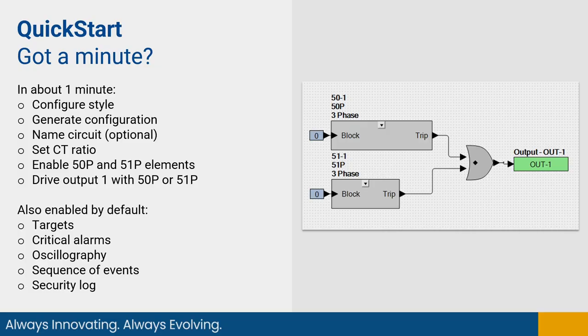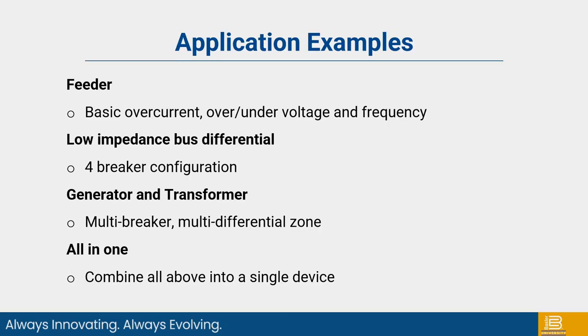The last step before saving the settings file would be to drag and drop the protective elements and other logic you may need and connect them on the logic page as shown on the right side of the graphic. Once these steps are complete and you save the file, you're ready to upload the settings file to your new BE1-FLEX relay with a simple overcurrent protection scheme.